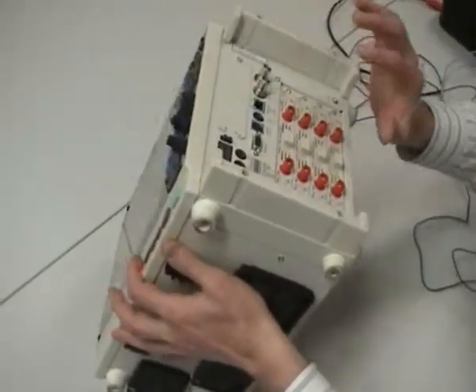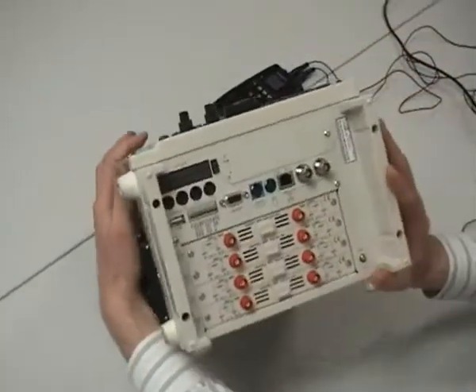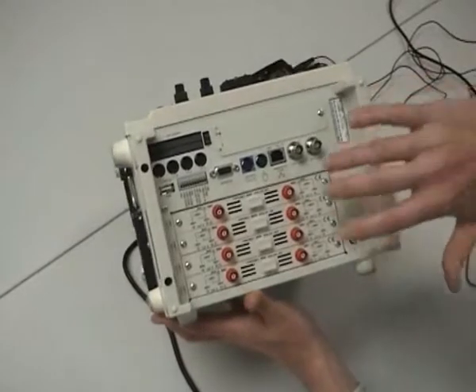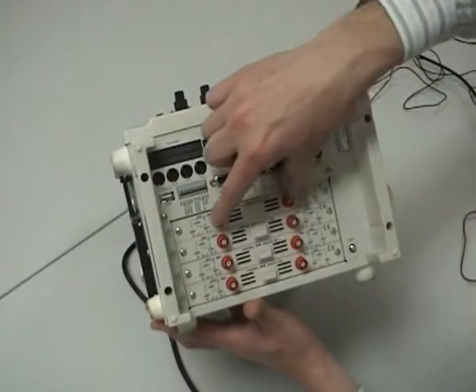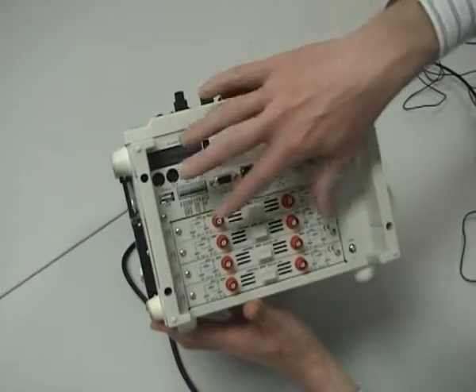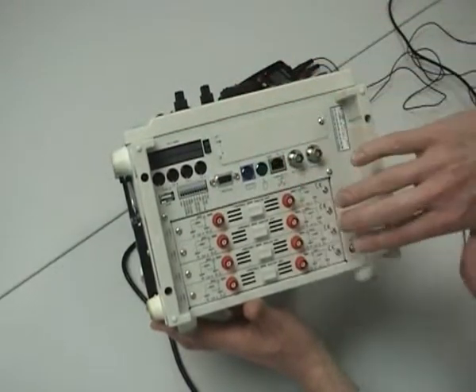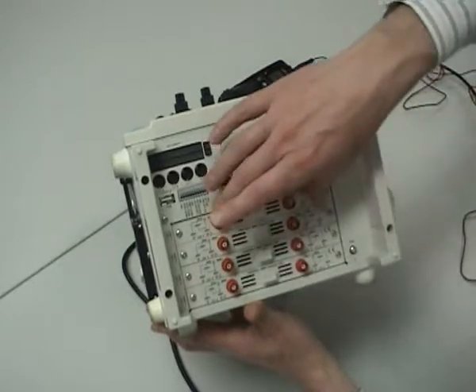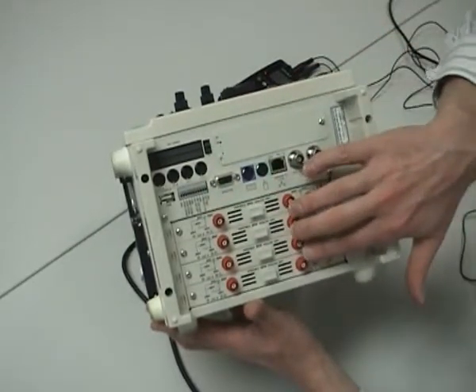On the side here we've got the channel information, so if I can just show that there, that way. So we've got analog input channels here. There are four slots. In this case, we've got a two analog channel unit up to 400 volts DC. And so configured with these analog inputs, you get eight analog channels.